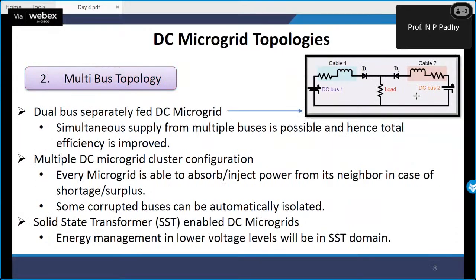Now, one more topology where we have two different DC sources being supplied and connected. This is known as multi-bus topology, where we have dual bus separately fed DC microgrids. Simultaneous supply from multiple buses is possible, and hence the total efficiency is improved. So you can have multiple DC buses catering to a single load.